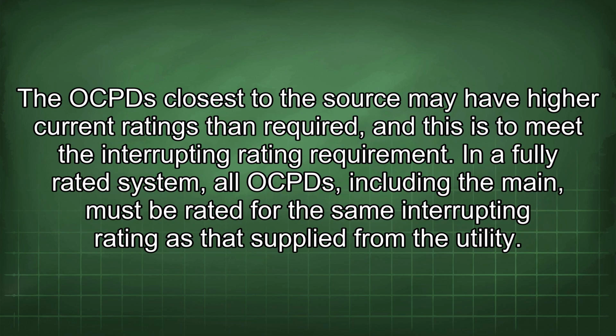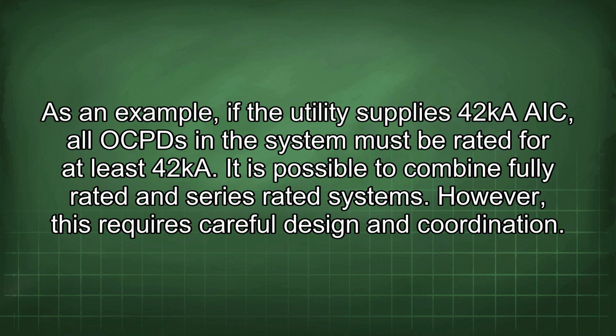The OCPDs closest to the source may have higher current ratings than required, and this is to meet the interrupting rating requirement. In a fully rated system, all OCPDs, including the main, must be rated for the same interrupting rating as that supplied from the utility. As an example, if the utility supplies 42K AIC, all OCPDs in the system must be rated for at least 42kA. It is possible to combine fully rated and series-rated systems.